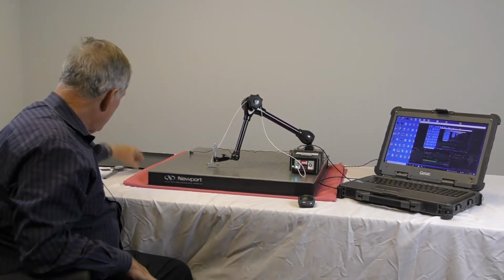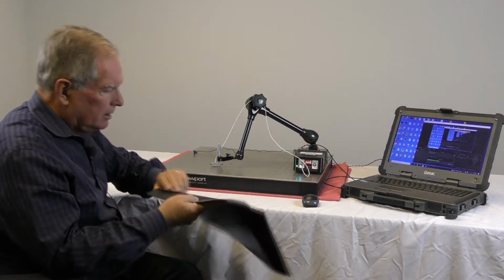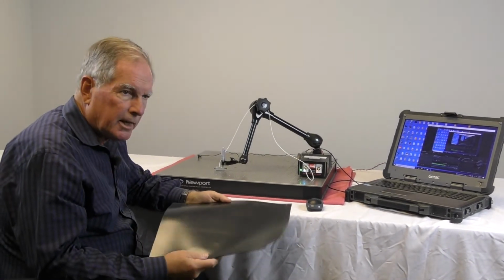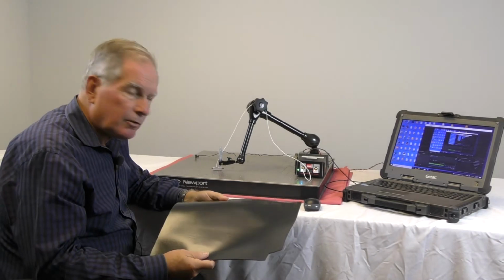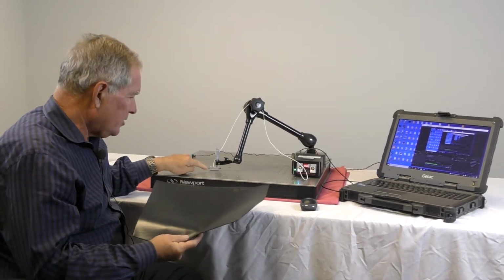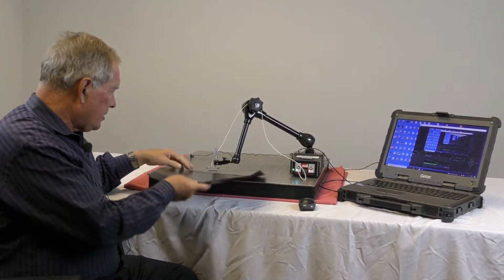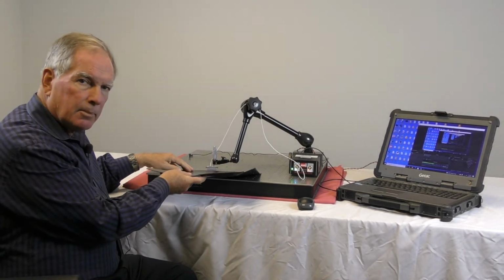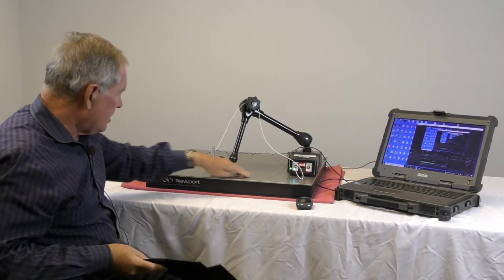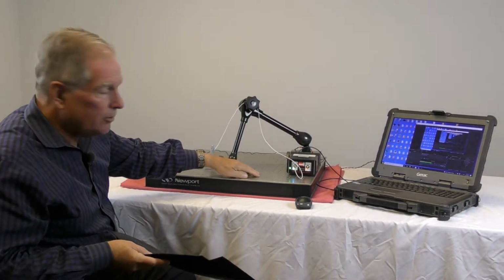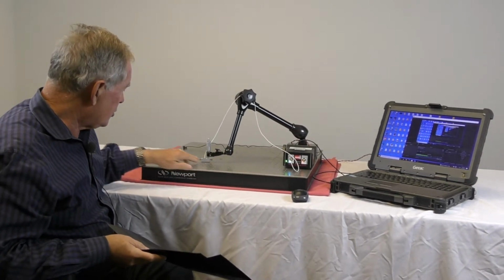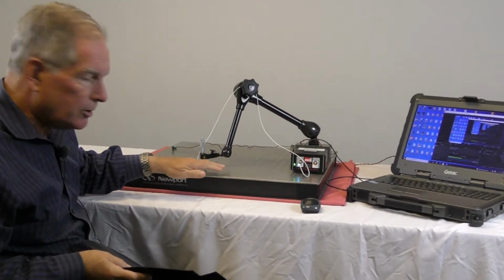So when we want to measure non-conductive materials, we're making the measurement by putting an electric field between the probe face and this ground plate, and then we're going to be sticking the material in between the two. In this plate you can see there are little tiny holes, and we've adjusted the probe so that no hole is underneath it.